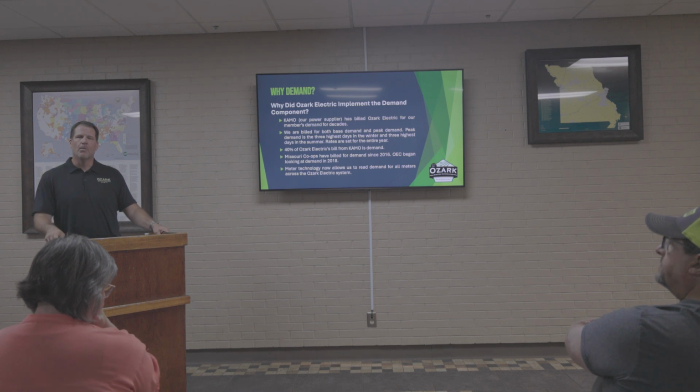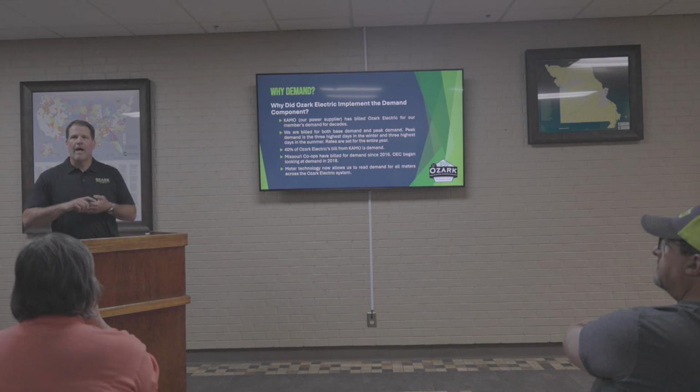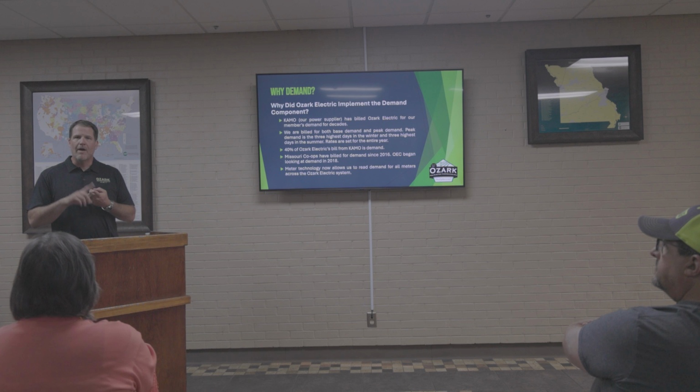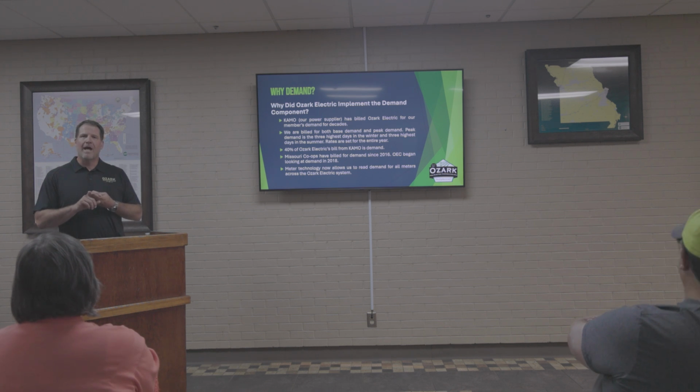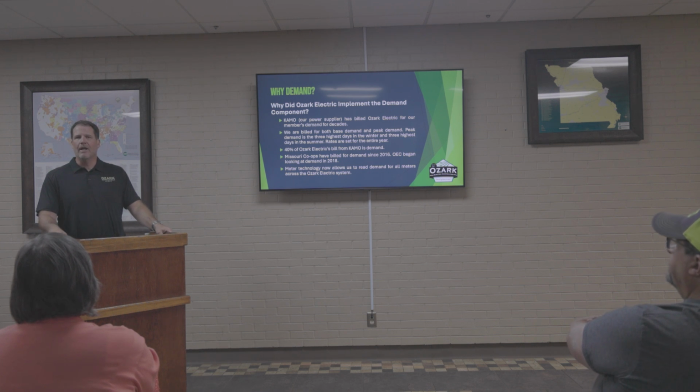When we go out to your home and we design the system for your needs, we don't say, how many kilowatt hours do you think you're going to need? We put a transformer in place for the demand that you're going to be asking of that. When the engineers go out, they're going to ask you what the square footage is, what the heating and cooling is, things like that. If you build a shop building, are you going to have a welder? Are you going to have an air compressor? Are you going to have these different things? So that demand is really what's important when building this system and what it's based off of, versus kilowatt hours.